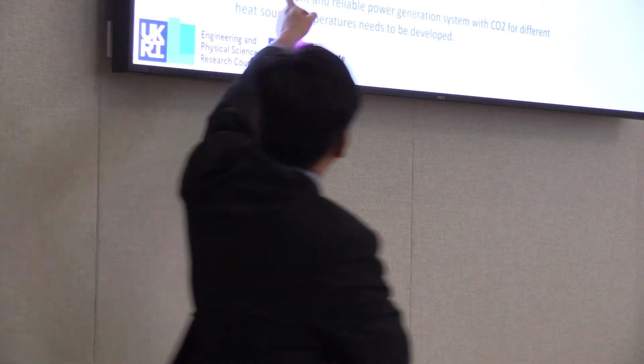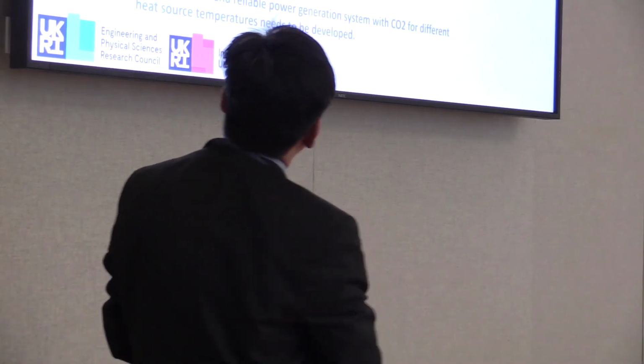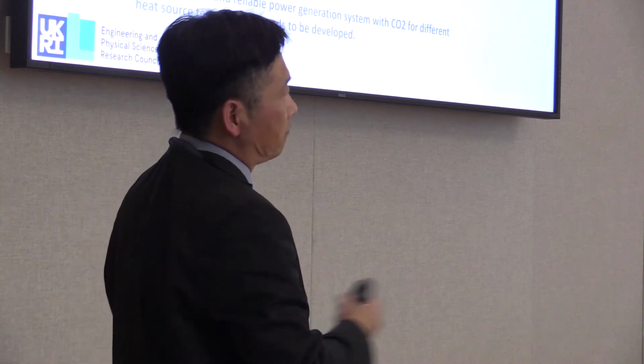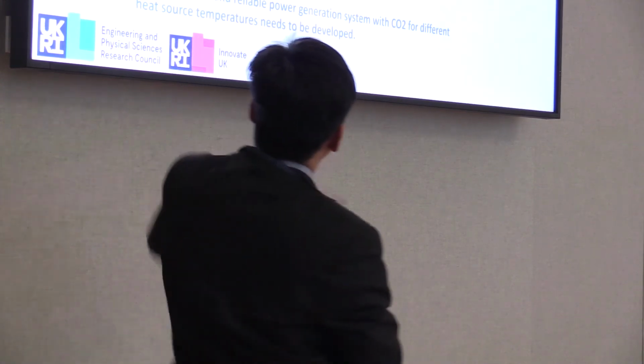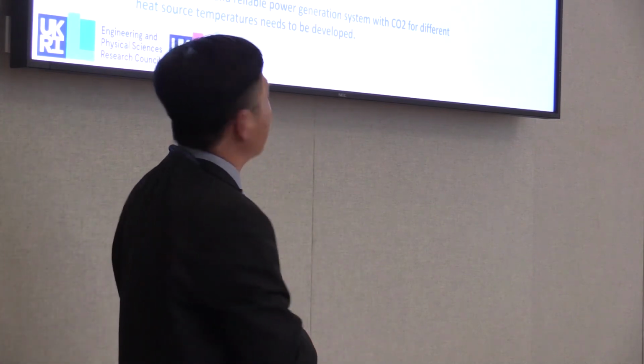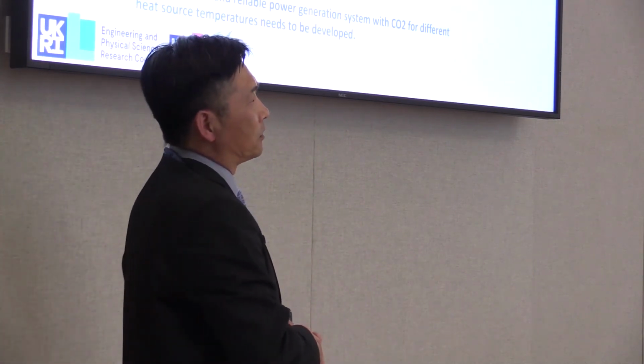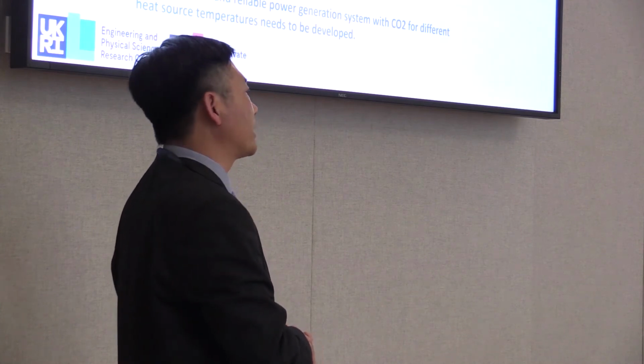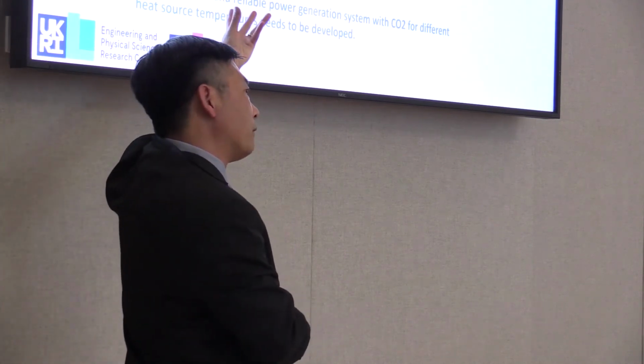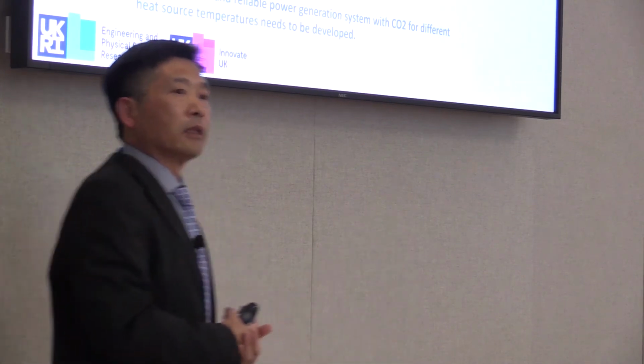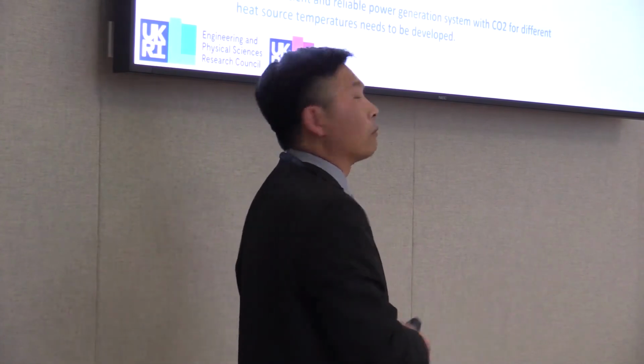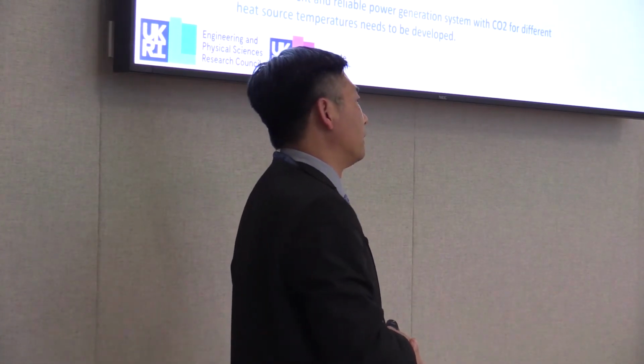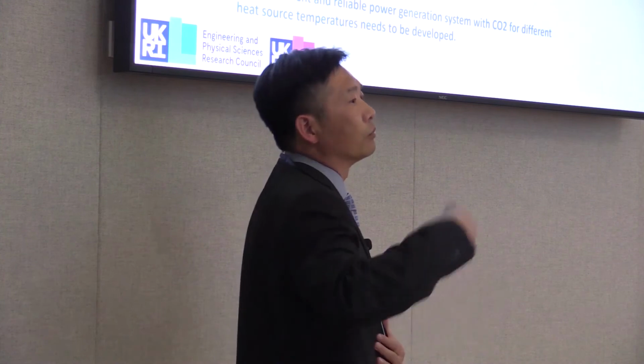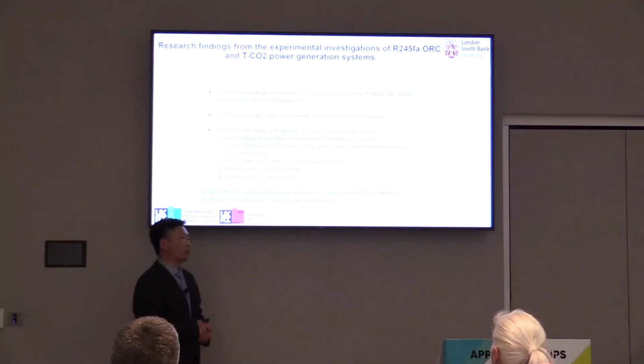And also what we found is the high power consumption of the CO2 liquid pump, some issue for that, and also the low efficiency of the CO2 turbine, and also leakage in the CO2 pump. So that is not practical. So we need to find an alternative way to pressure up the CO2 from low pressure to high pressure. Instead of using the liquid pump, maybe we can think about using a compressor, because a compressor is easier to find on the market, but you need to change the design of the power generation system if you are using the same working fluid, CO2.